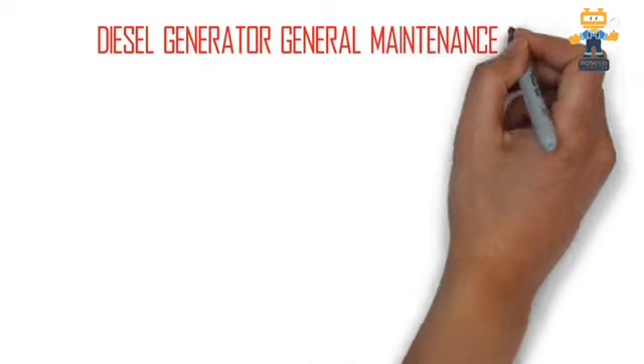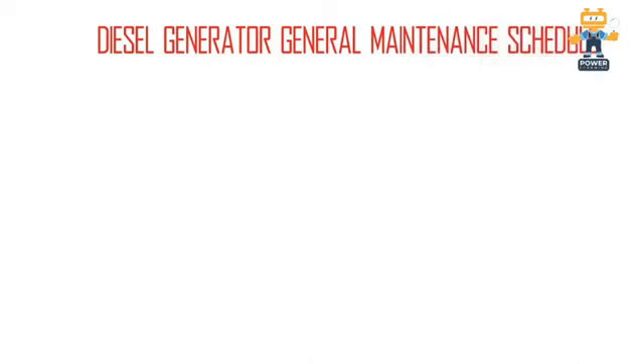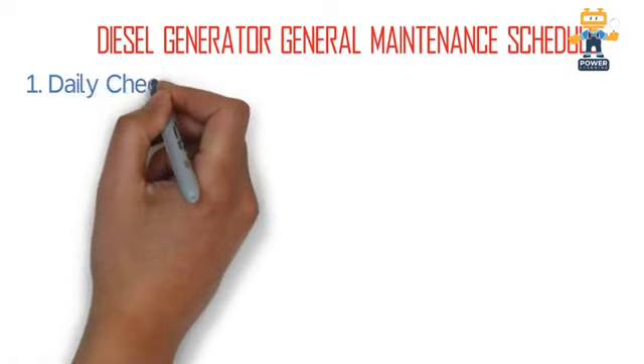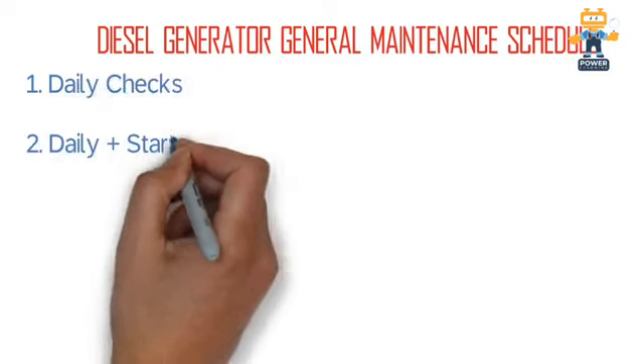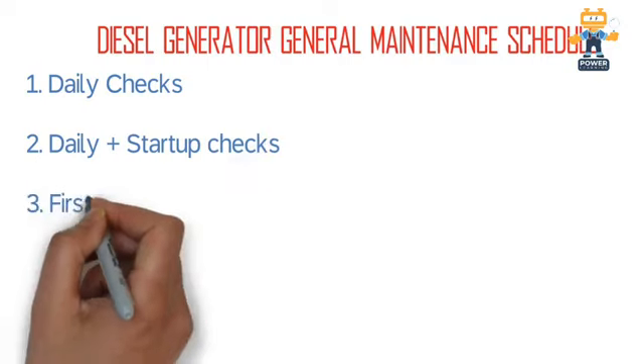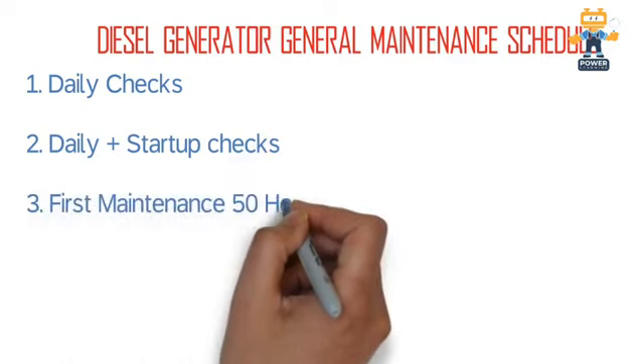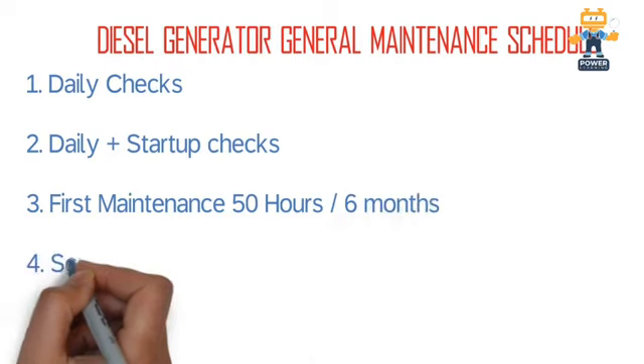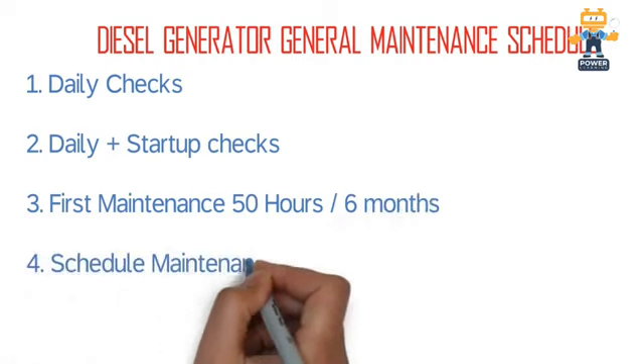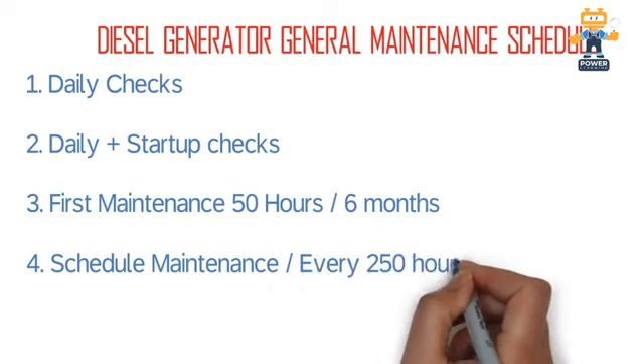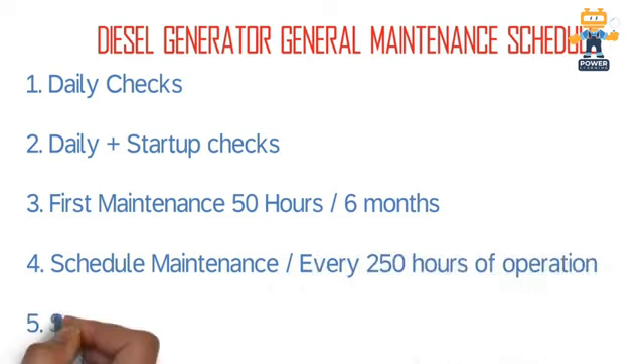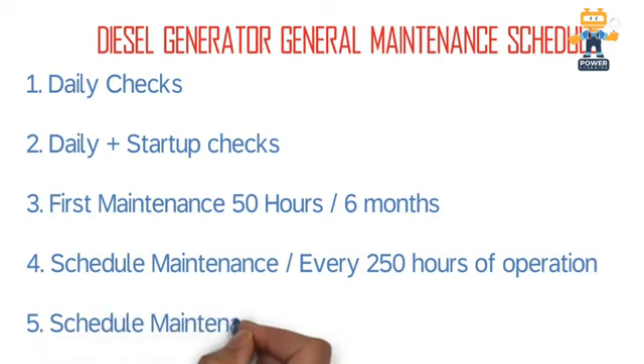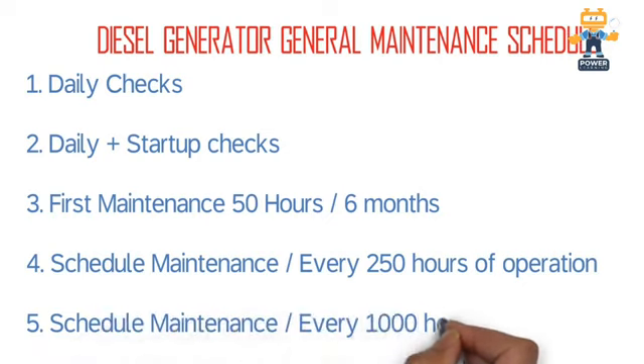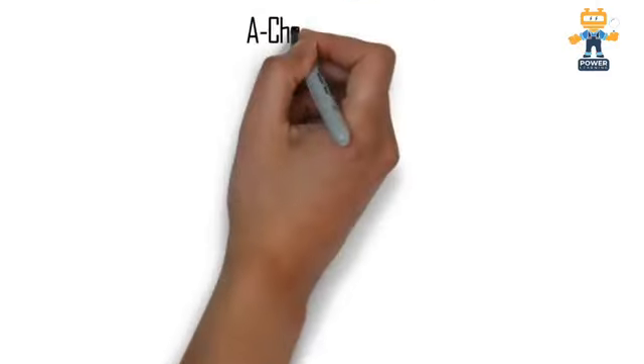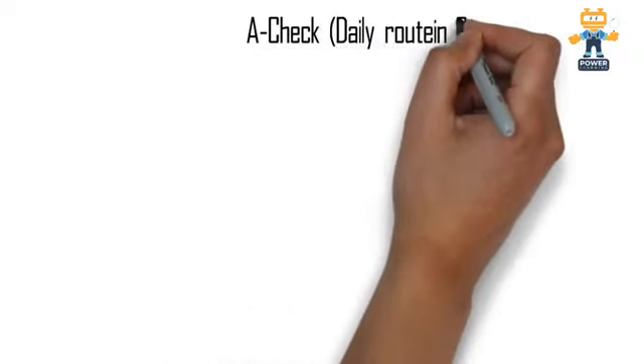So today's video topic is the diesel generator general maintenance schedule. In this video I am going to show you all the points required for diesel generator maintenance. We have number 1, daily checks; number 2, daily plus startup checks; number 3, first maintenance at 50 hours or at 6 months; number 4, scheduled maintenance every 250 hours of operation; and number 5, scheduled maintenance every 1000 hours of operation. In all these 5 points we will cover all the major maintenance points required for the diesel generator.